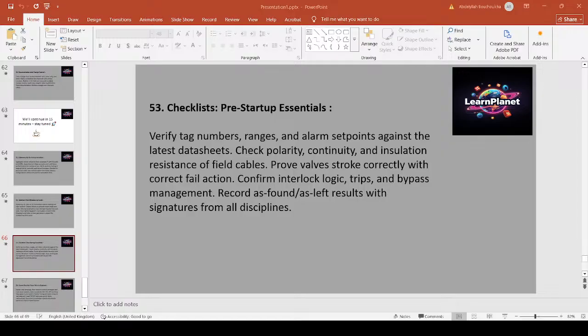Before startup, verify tags, ranges, alarm set points, cable polarity, continuity, insulation resistance, and valve fail action. Perform loop checks from field sensor to DCS. Simulate trips and record as-found, as-left values with responsible signatures. Confirm interlocks and bypass management are correct and that documentation is current. Example: before first oil, perform a pre-start checklist covering all safety and control loops. Record results and obtain discipline sign-off.